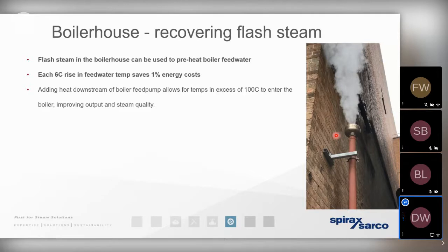And not only are we likely to have flash steam vented away, it is likely that any failed open steam traps will also be vented away to atmosphere from the same point. So we want to keep an eye on our flash steam vents. And if we see a significant amount of flash steam being vented away periodically, then it tells us there's an opportunity to do something about it. Because, as we've mentioned previously, there's just as much energy in a kilogram of flash steam as there is in a kilogram of plant steam.